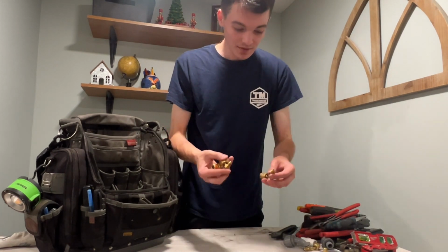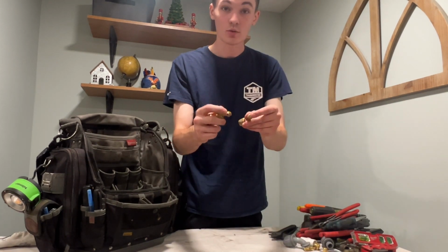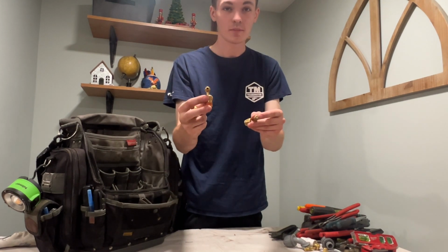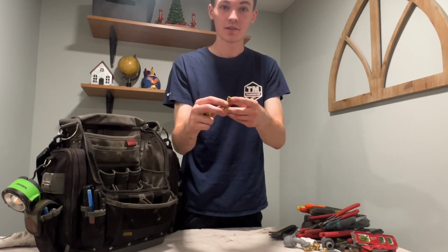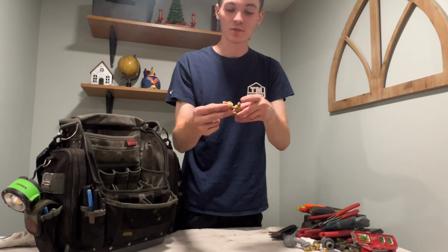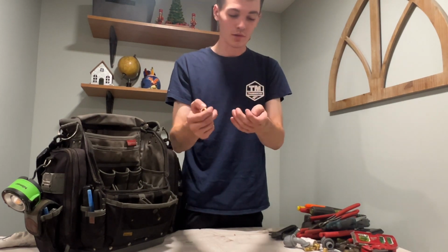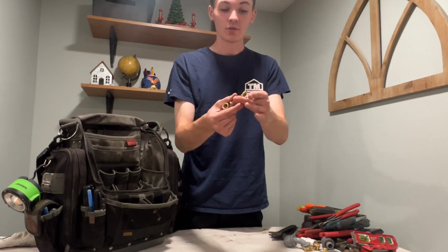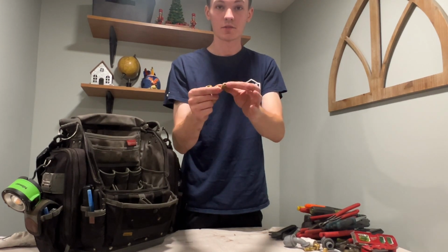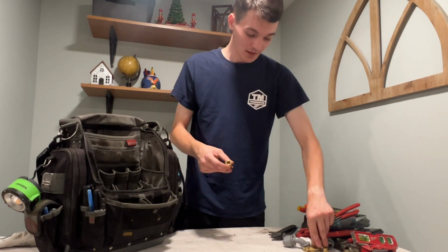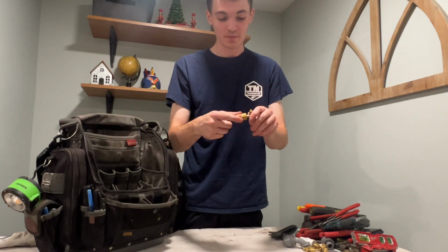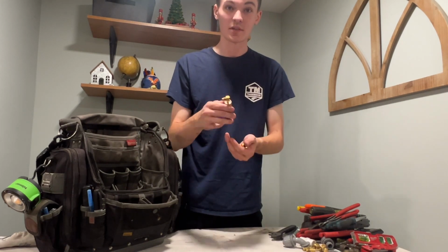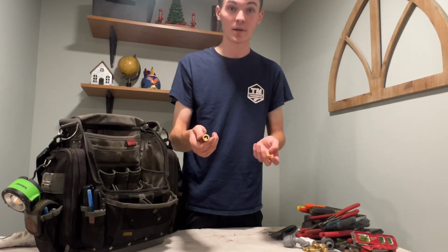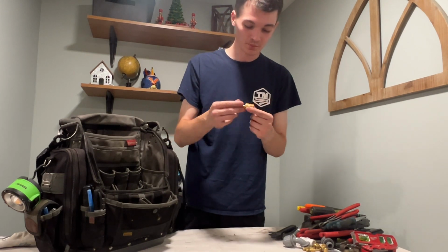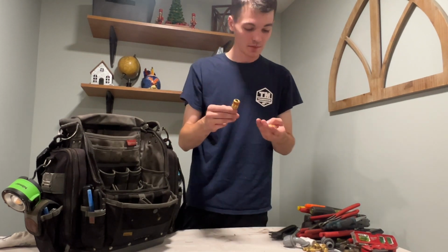The downside of these is that the 1/4 inch connection on the anti-blowback doesn't have a Schrader core, so you have to be connected to your hose in order to hook this up. Whereas with the Yellow Jacket, you can hook it up and then connect to your hose because it has that Schrader port. But these are very beneficial in minimizing refrigerant loss and minimizing burning your fingers if, say, it's operating in heat pump mode and the pressure is really high. I do like these a lot, and they come in handy.